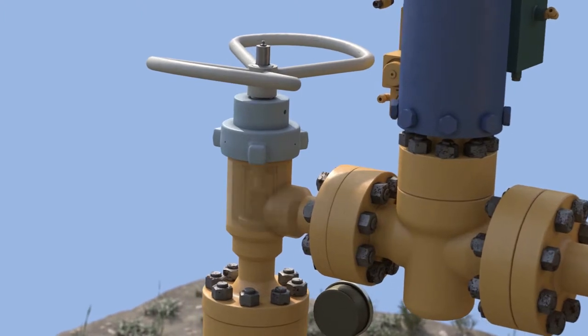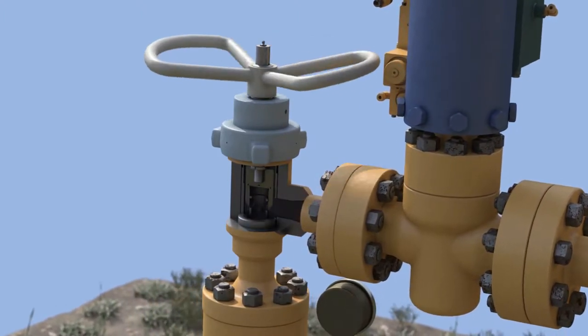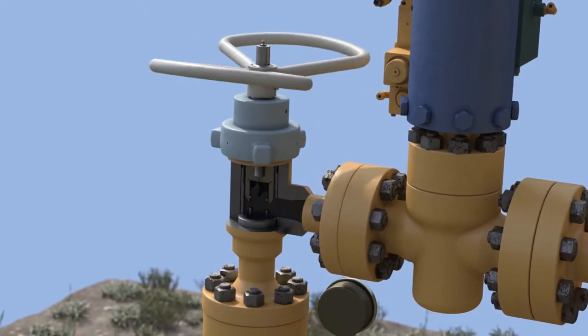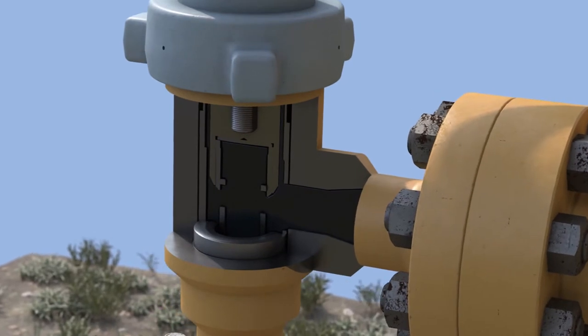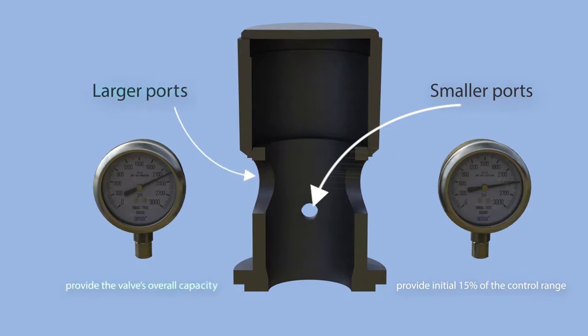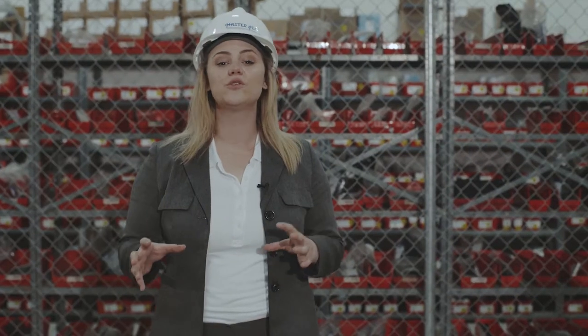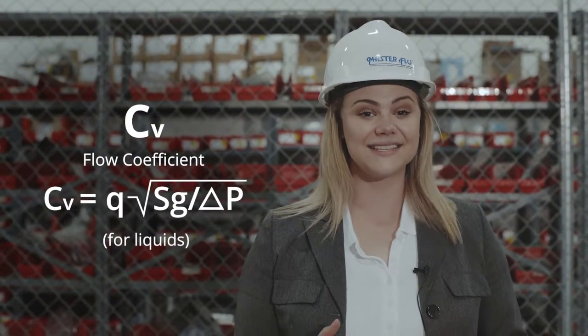MasterFLOW's standard trim provides a high level of control over its life. The smaller, lower ports provide the initial 15% of the control range, while the larger ports provide the valve's overall capacity. This results in an equal percentage flow characteristic curve and high liquid pressure recovery factor.